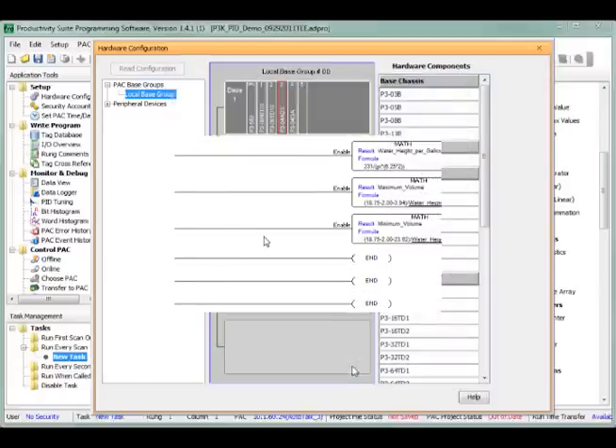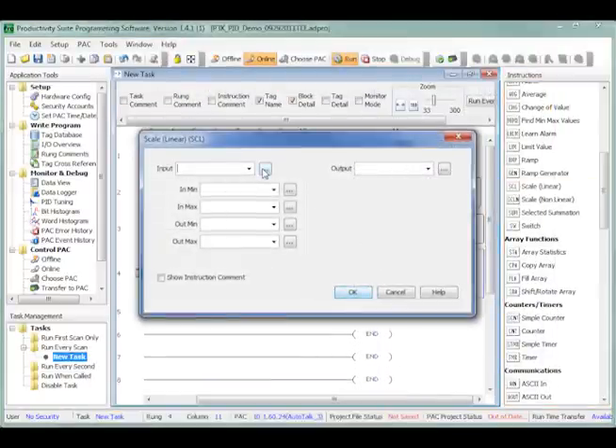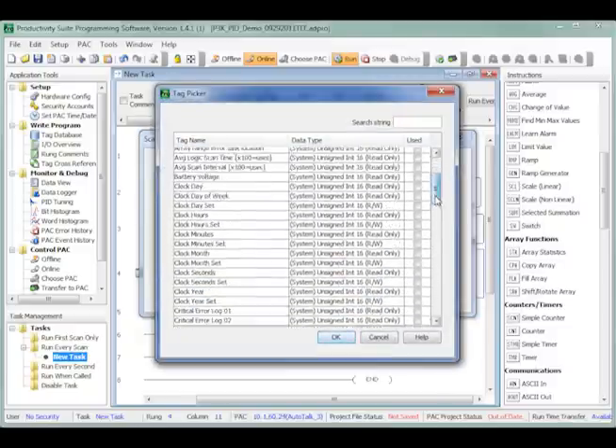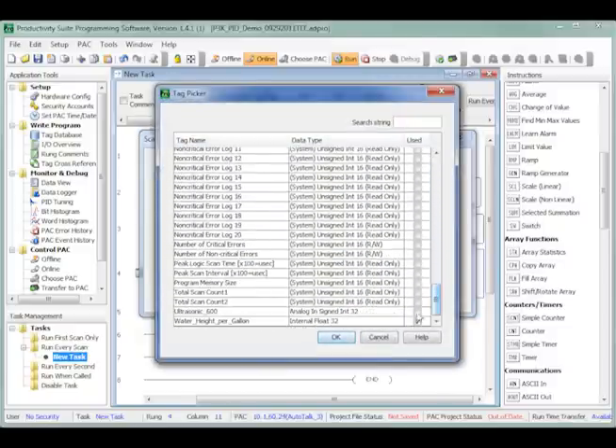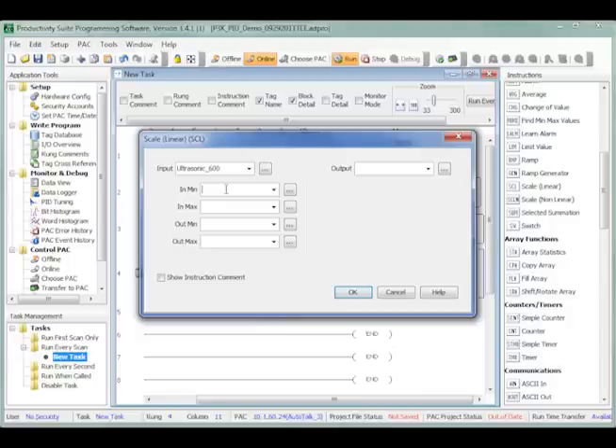Next, drag and drop the scale linear instruction into the next available end coil position on the ladder logic — in our case this is rung number 4. The scale linear instruction dialog window will open. Insert the new tag name ultrasonic_600 into the scale instruction input parameter. It will produce a count range of 0 to 65,535, so for the In Min parameter we enter 0, and for the In Max parameter we enter 65,535.